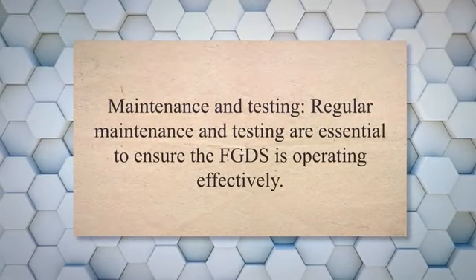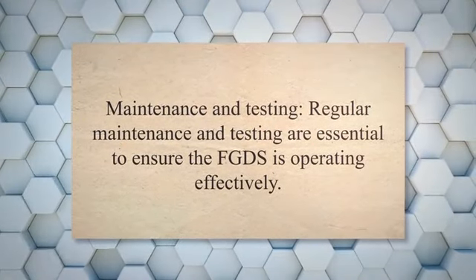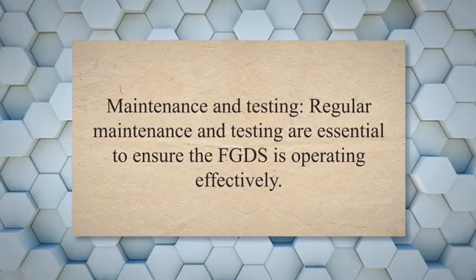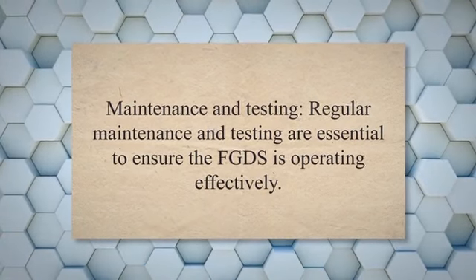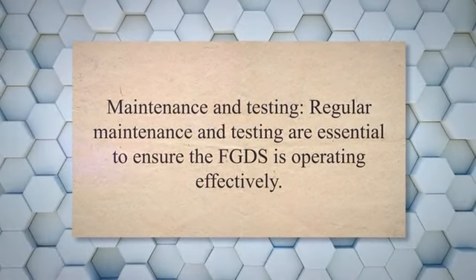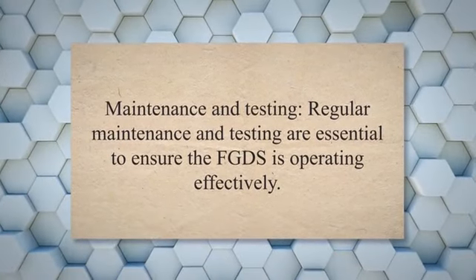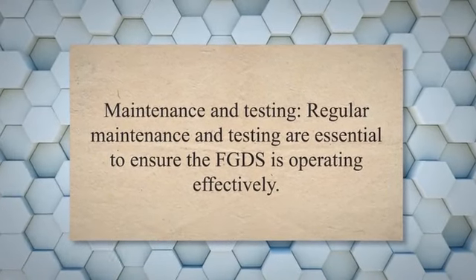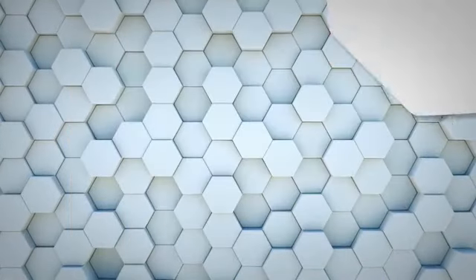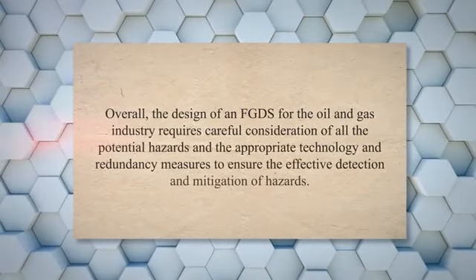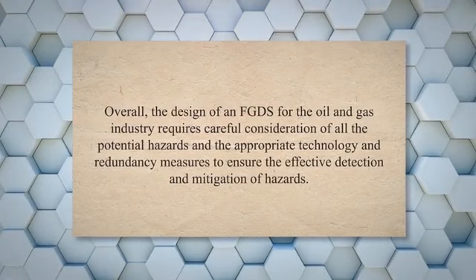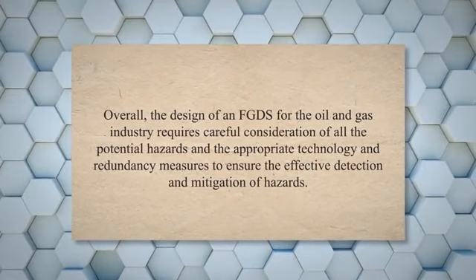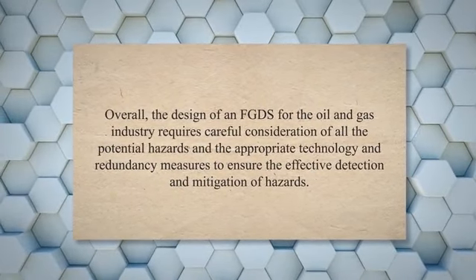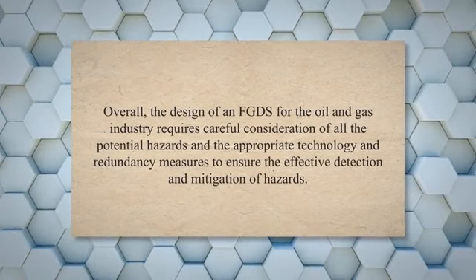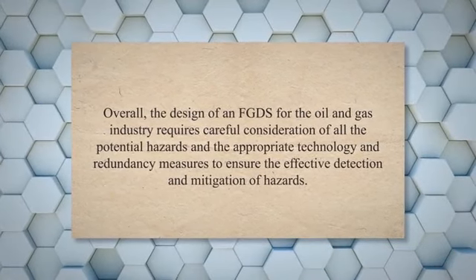Maintenance and testing. Regular maintenance and testing are essential to ensure the FGDS is operating effectively. This includes regular calibration of sensors, testing of alarm systems, and conducting regular drills to ensure personnel is familiar with the system and its operation. Overall, the design of an FGDS for the oil and gas industry requires careful consideration of all the potential hazards and the appropriate technology and redundancy measures to ensure the effective detection and mitigation of hazards.